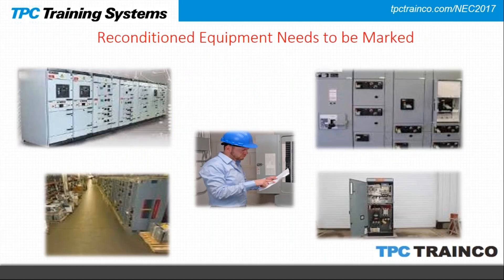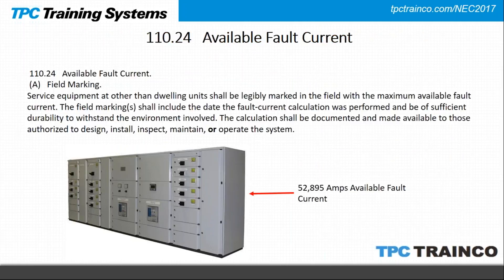Section 110.24 deals with available fault current at service equipment, other than dwelling units. They added the word 'or' — if equipment is installed, refurbished, or modified, the available fault current must be marked on the service equipment. The calculations shall be documented and made available to those who design, install, inspect, maintain, or operate the system. Available fault current is critical — whether we're trying to eliminate arc flash hazards or coordinate a system, we have to know that value.